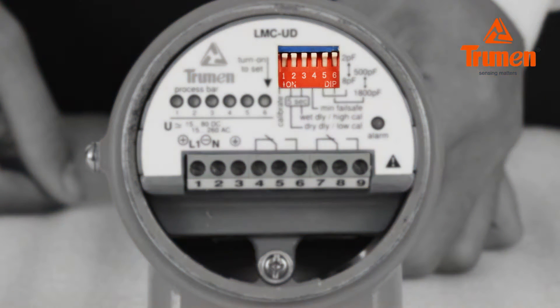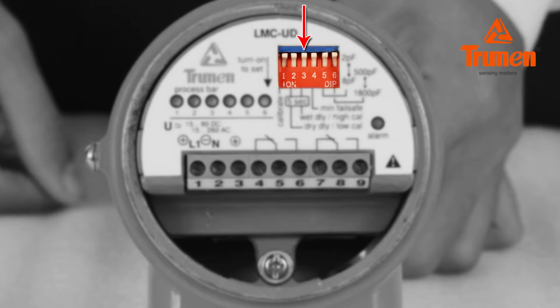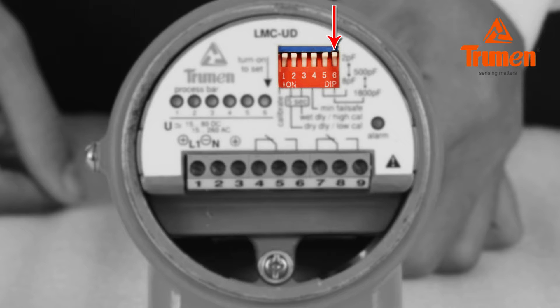There are six DIP switches on the connection panel. DIP switch one is used to calibrate the instrument in air or in material. Switch two sets dry delay. Switch three sets wet delay. Switch four sets fail safe. Switch five sets sensitivity: 2 pF or 8 pF selectable.